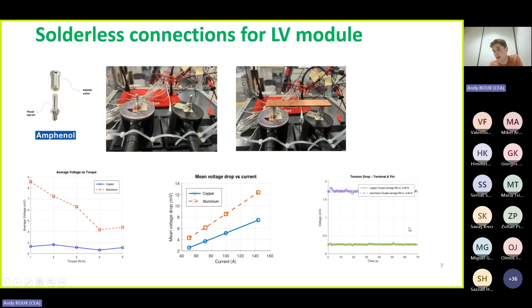We also did this for the cam lever, where the voltage drop is really low. What's interesting with this solution is that if you imagine a fork bus bar, when you release the cam lever, you can just pull out the bus bar and change the cells or anything else. Because we have a really low voltage drop, even at 100 amperes during 1 minute, the temperature rises just 0.2 degrees, so the connection was really good.